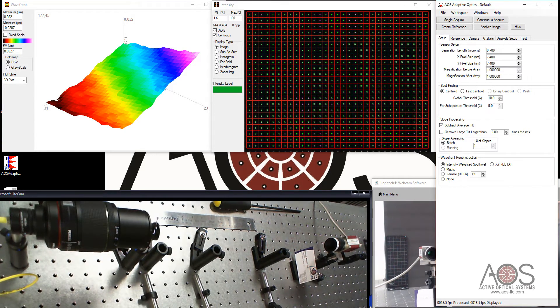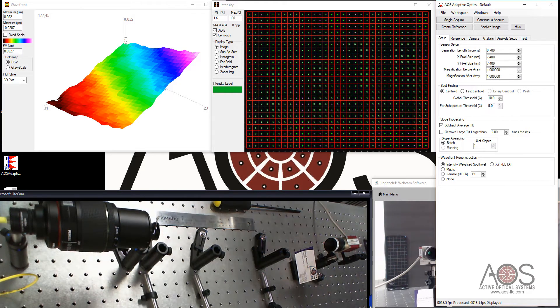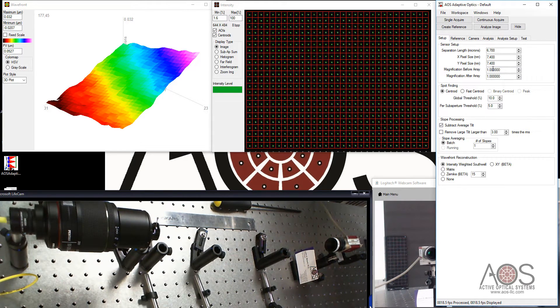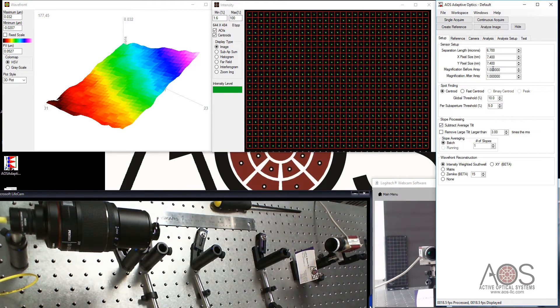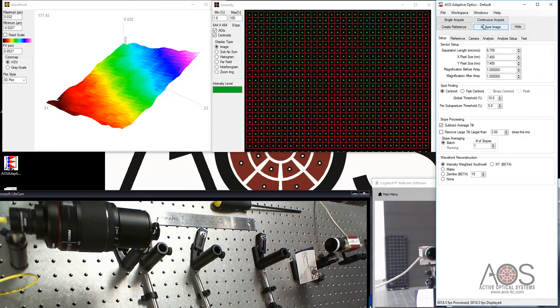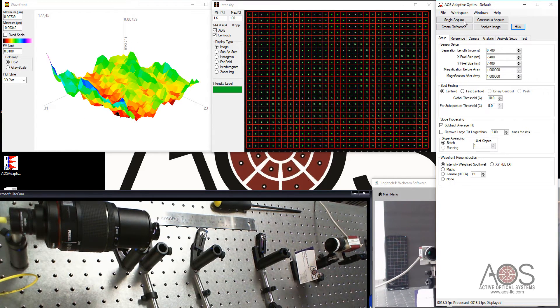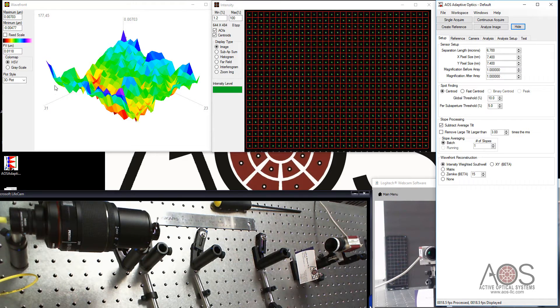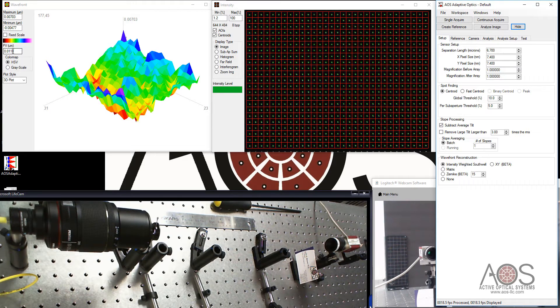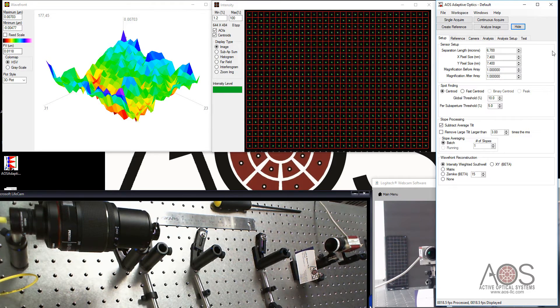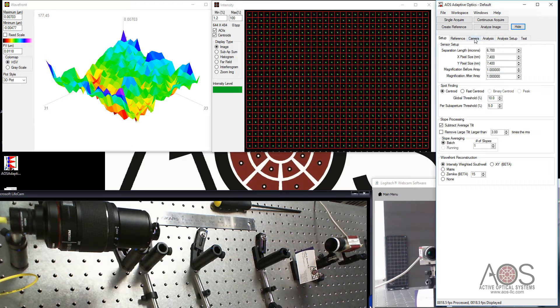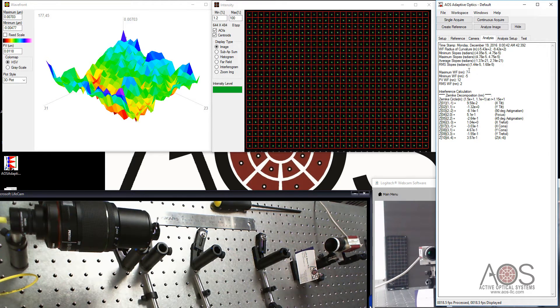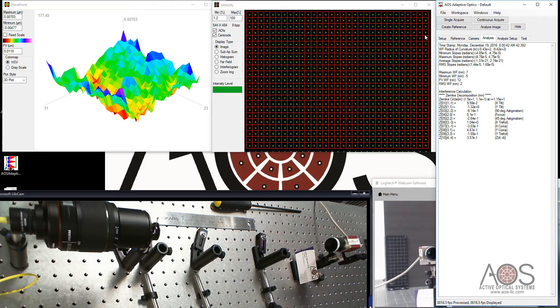So now I'm seeing a tilt term, which is normal in the lab. I also have the HEPA filters on over the table, so I'm going to turn them off. Gets a little less noise on the table when I'm making measurements. I've subtracted average tilt. And now we're seeing some background noise on the order of 12 nanometers peak to valley. You can go to Analysis here, and we can see that a couple nanometers RMS for this condition. We're in really good shape.